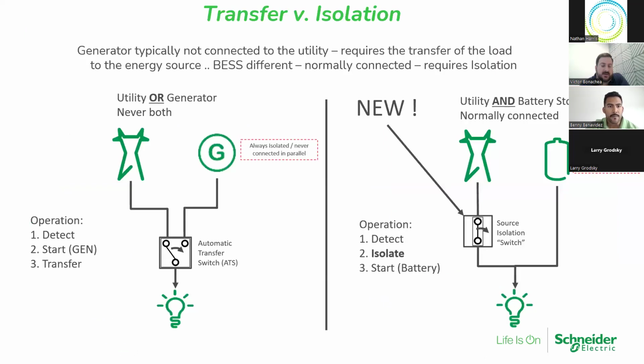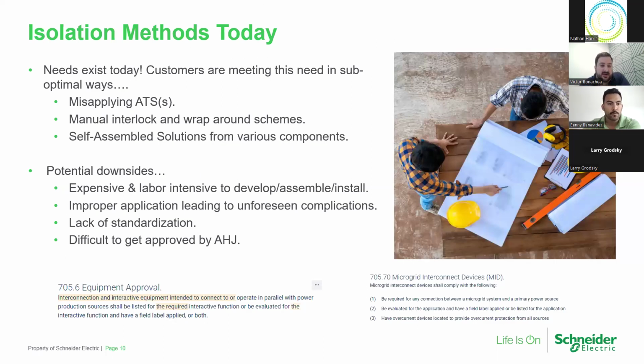Yeah, especially as the National Electric Code now is allowing microgrids and battery energy storage systems to be used to feed power to emergency standby systems. One of the code excerpts on the previous slide mentions that one of the requirements is when you're using it for an emergency standby application, it must be listed for that application. So a lot of the options here are either products that are not listed for that because it's a different type of product, such as an ATS, which doesn't do that kind of sequence of operation, or it's a self-assembled solution or a custom solution done by an integrator that probably doesn't have a standardized UL listing, which can make it very difficult to pass any sort of inspection, rather than a purpose-built device for that application and listed for that application as well.